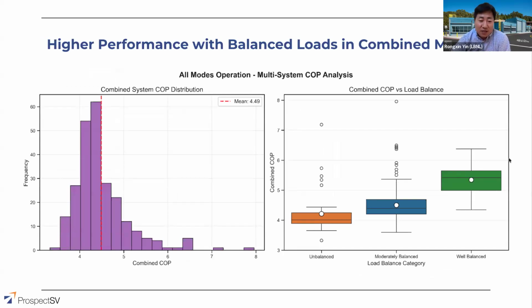All right, so this is a supplemental slide about combination mode system performance. As we can see, when the system is at well-balanced load conditions, the average COP can range around 5.5, from 4.3 up to 6.5 with a well-balanced load. And if the unit is running cooling dominant or heating dominant, there are unbalanced load conditions, and the average COP ranges between 4.3 and 4.5 for the overall unit performance. And let's move on to the next slide.